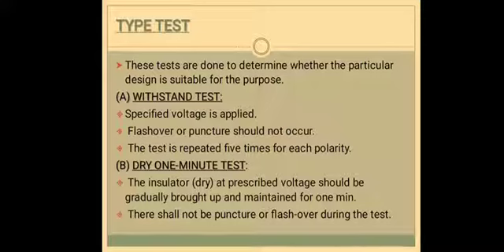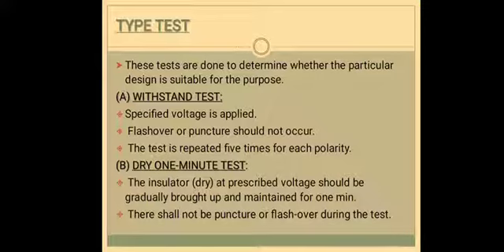With the type test, these tests are done to determine whether a particular design is suitable for the purpose or not. First is the withstand test — only a specified voltage will be applied, with a wave of 1/50 microseconds. Flashover or puncture should not occur, and this test will be repeated 5 times for each polarity.